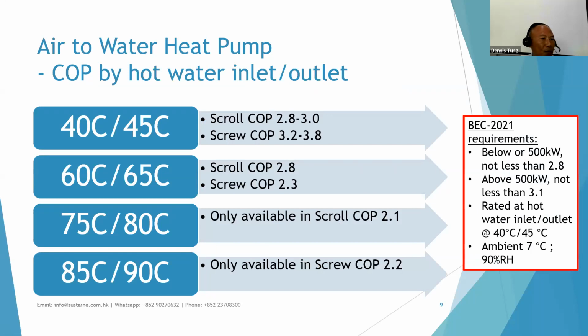So nowadays we have very good heat pumps. Heat pumps have different outlet temperatures with different COP. With a leaving temperature of 45 degrees, the COP will be up to 3.8. With a higher temperature, the hot water temperature up to 90 degrees, the COP will drop a little bit. Although the temperature rises and the COP drops, the COP is still 2.1 to 2.2. That means if I input 1 unit of energy into this system, I will have 2 units of heat energy for use in the building. So this is still a benefit of using a heat pump for high temperature applications.